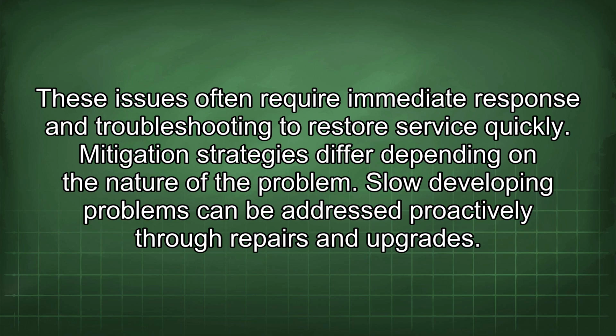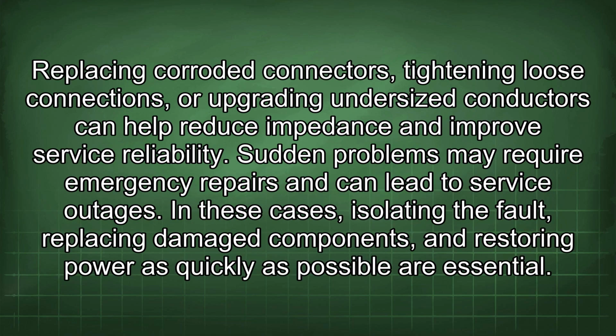Mitigation strategies differ depending on the nature of the problem. Slow-developing problems can be addressed proactively through repairs and upgrades. Replacing corroded connectors, tightening loose connections, or upgrading undersized conductors can help reduce impedance and improve service reliability. Sudden problems may require emergency repairs and can lead to service outages. In these cases, isolating the fault, replacing damaged components, and restoring power as quickly as possible are essential.